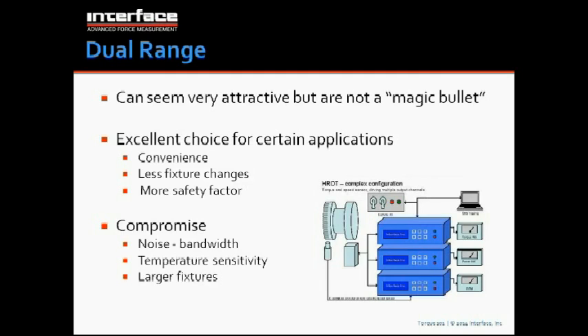And also you end up using larger fixtures. Imagine if you're trying to test 2 different pump sizes, but you're using a dual range sensor. You're always going to be using the full size sensor even to measure the small pump torque. And so the couplings and the fixturing you use to adapt to the small shaft are going to be dictated by the large form factor of the upper size of the range sensor.